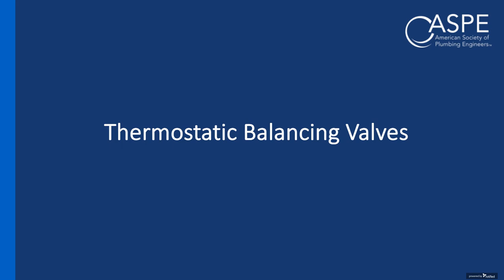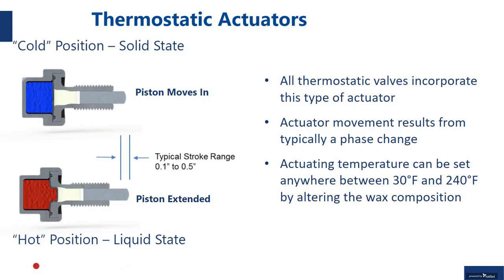So let's get into thermostatic balancing valves, which is what we're here to talk about. And first off, every thermostatic type of valve is centered around a thermostatic actuator. Typically they're paraffin wax. They could be some other type of material, but typically they're paraffin wax. So this diagram shows two representations of a thermostatic actuator. The one at the top, left in the blue, is the actuator with the paraffin wax in a solid position. At the bottom is the same actuator with the paraffin wax in a liquid position.